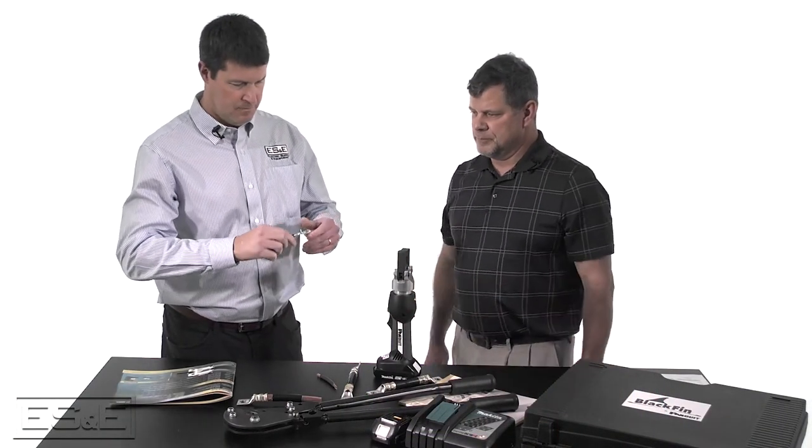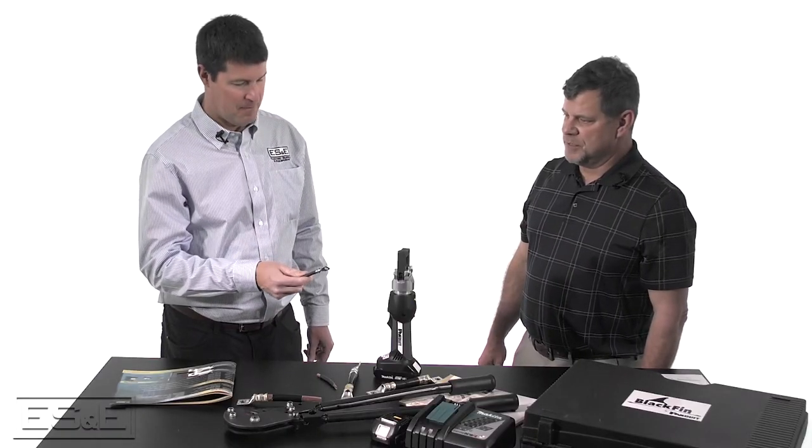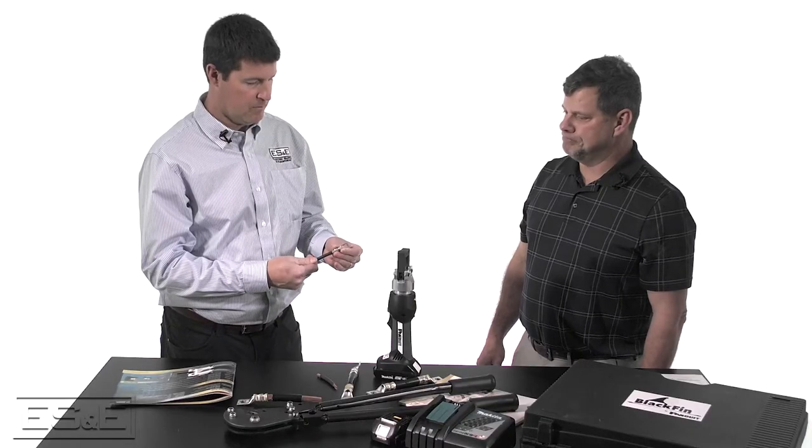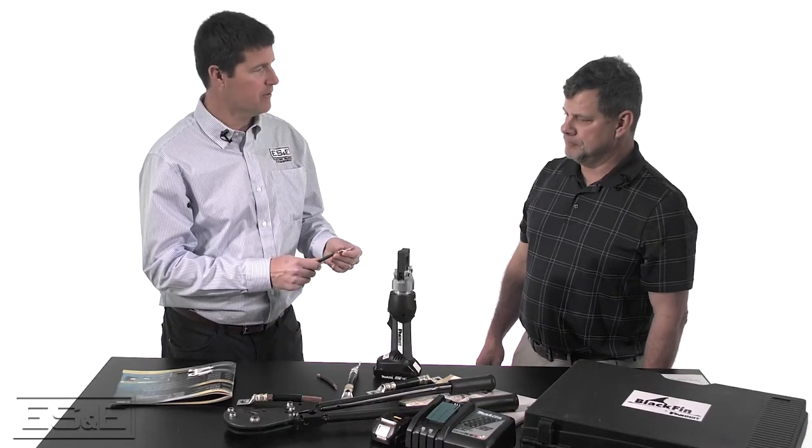And your second crimp. All right. That's on there pretty good. Yeah. With a four ton crimp, that's going to give you a UL, CSA approved crimp with four tons of pressure. Okay. So this is considered a controlled cycle crimp. Yes.